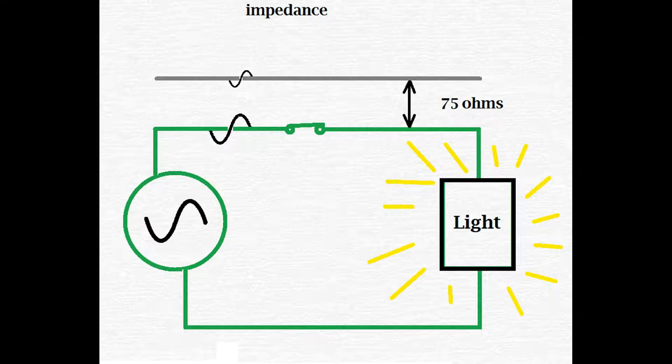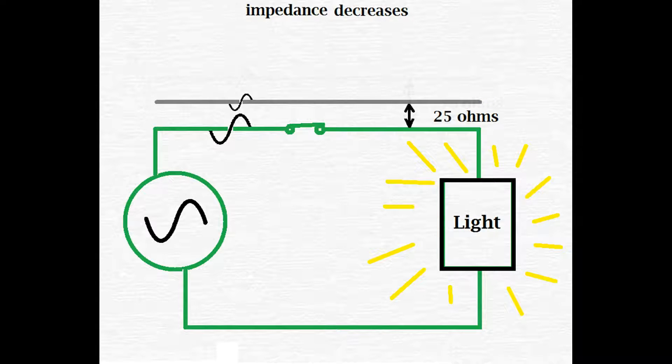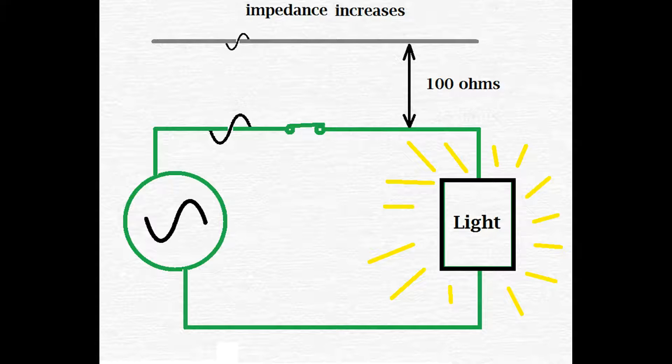So, for example, a wire this far away could have 75 ohms of impedance. Move the wire closer, and it's easier to transfer the signal, so your impedance has dropped. Vice versa, move the wire further away. It's harder to transfer your signal, so your impedance increases. What the TDR is designed to do is to measure this impedance, or the distance the wires are apart from each other.